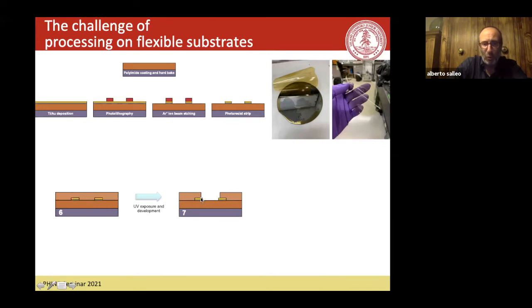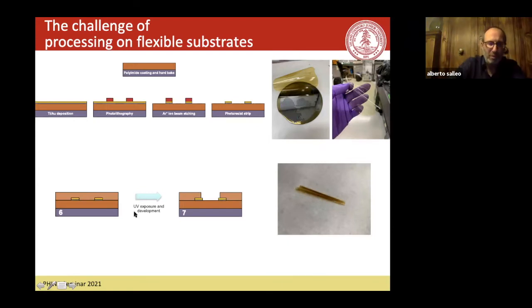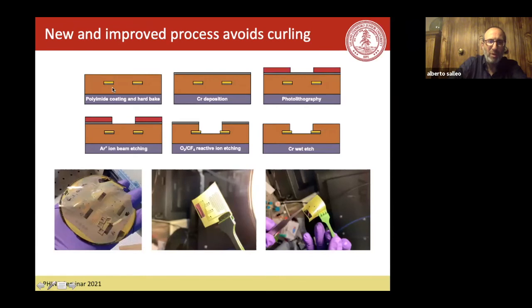So you have to do what is called opening a window or cutting a window. Once we did that, actually it was even worse, because this polymer, which was different so they could be photo-defined, had a different thermal expansion coefficient from the polyimide, and so this curled it even more, because now rather than just having two small metal lines, we had a whole layer on top that made it curl. And so the solution, as you can imagine, is to use the same polymer top and bottom. So we developed a recipe to use polyimide top and bottom.